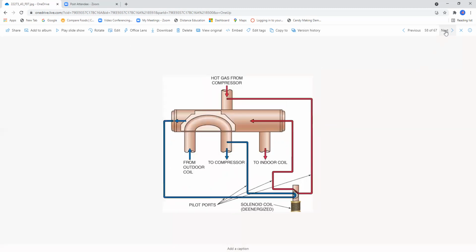Okay, now with the solenoid still de-energized, notice the flow of refrigerant. We're actually taking hot gas from the compressor. We are now going through the de-energized coil, and basically the refrigerant is blocked from going this way. So we are now going to the indoor coil and we're causing heat to take place.